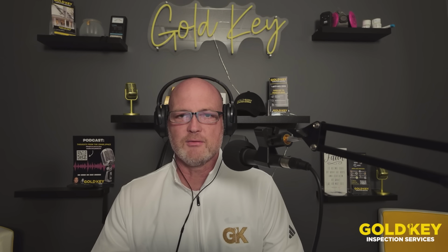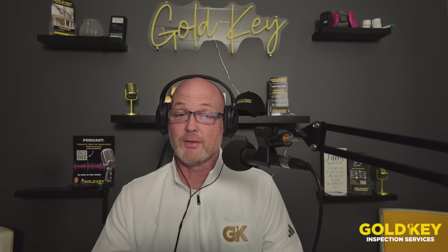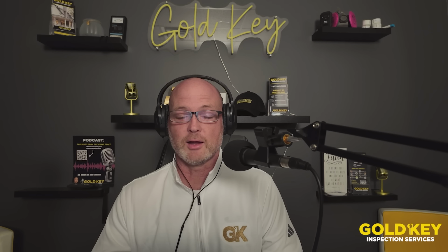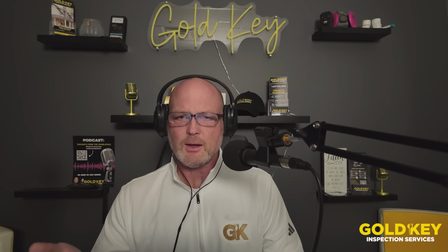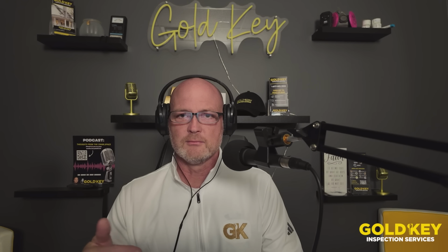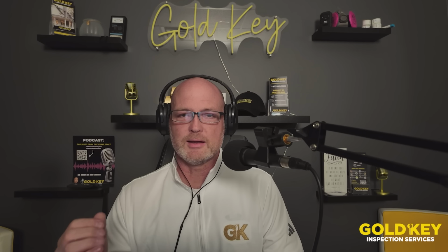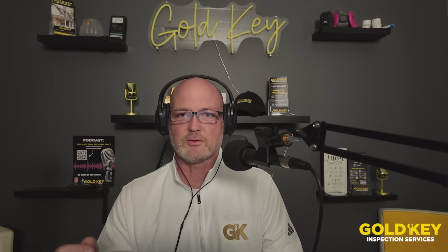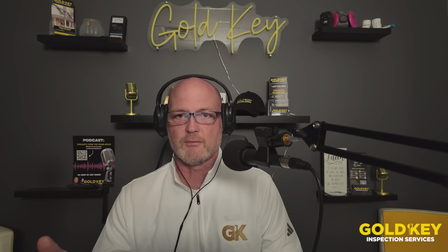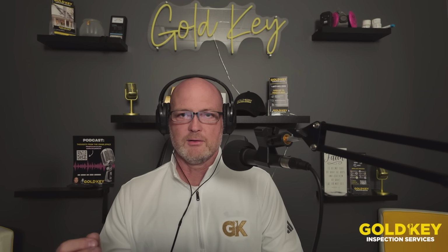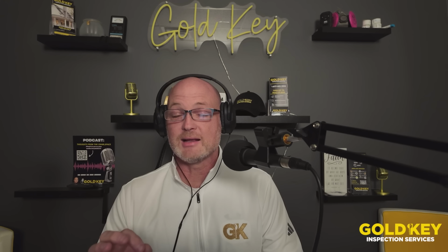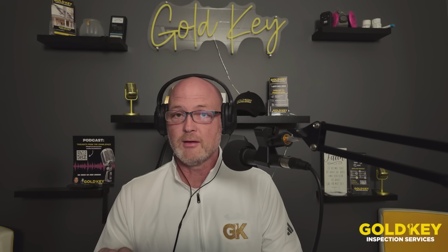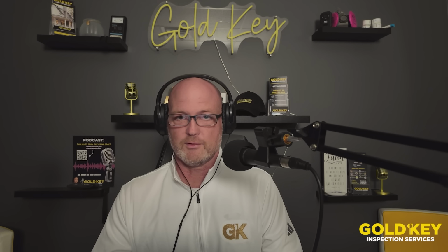Number 1, your humidity factor is going to still be relatively high in the house, even though it's summer and it's cooling. Number 2, your air conditioning is turning on, off, on, off. And that's what ultimately kills an air conditioner, is the electrical components turning on and off. So it's actually better to have an air conditioner that is just slightly undersized than one that would be oversized.